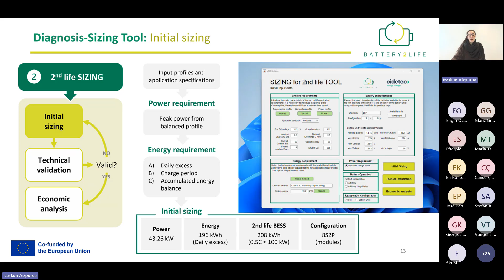So now we validate the operational limits, checking the voltage range, current limits, life expectancy, and full equivalent cycles. This way we can define if those limits are respected, validating the technical feasibility of the solution. If some limits are overpassed, we go back to the initial sizing and make it less restrictive.